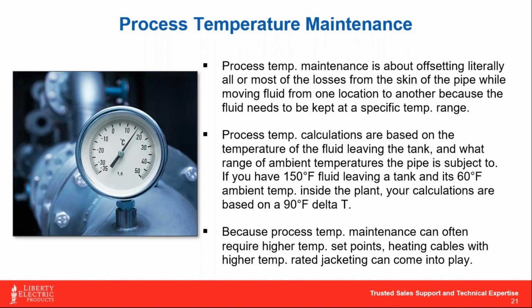So again, just a simple example that we did in the text of this slide: if you had 150-degree fluid leaving a tank and it's 60-degree ambient temperature inside of your plant, you're now basing this off a 90-degree delta T. Okay?